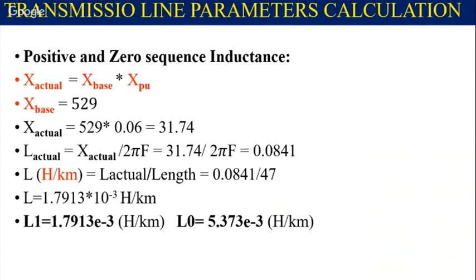Positive and zero sequence inductance we have to calculate similarly. Again, the actual value of inductance is base into per unit value. Base value is 529, as we have calculated. X actual, that is the inductive reactance, per unit value we know is 31.74, but it is reactance. We want the values in inductance, because in the pi section we require inductance in Henry per kilometer.